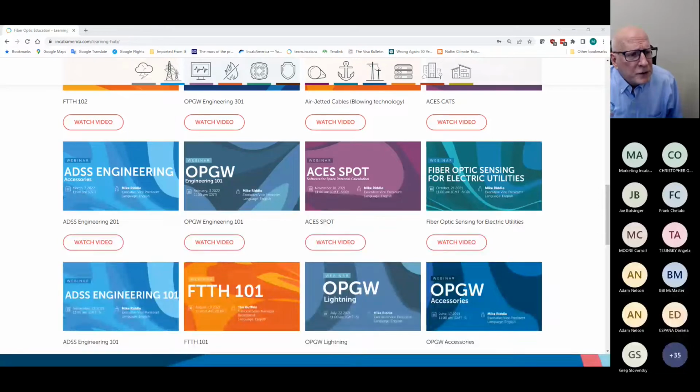Someone says, but IEEE 1222 refers to the pollution index. Yeah, but I can't go into that in detail today. It's like with lightning on OPGW. People talk about isokeraunic level, but that's not what really kills a cable. It's how many coulombs hit the cable and how often that becomes another factor in terms of optical reliability. So you can talk about pollution in a general sense, but the real factor is how much is really ending up on my cable.